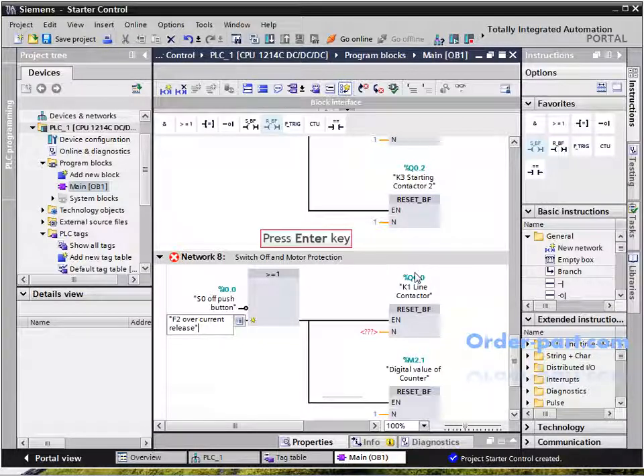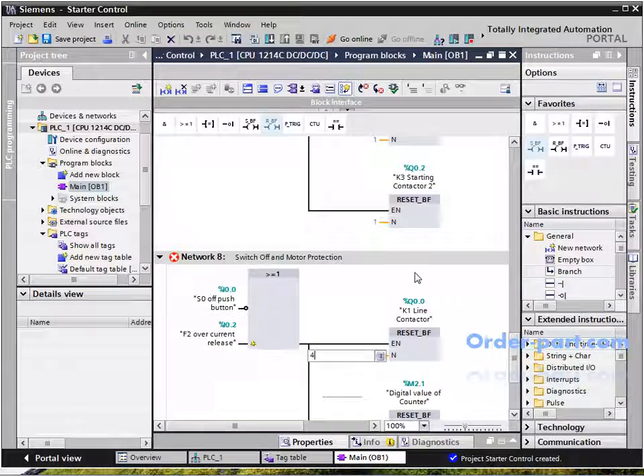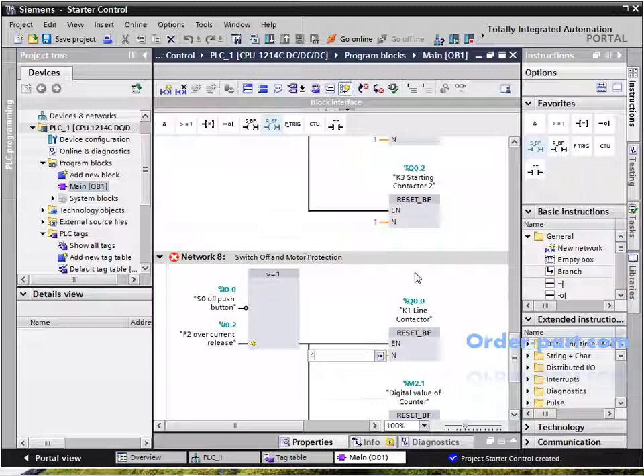In Network 8, if I0.0 is off or the F2 over-current release button I0.2 is on, it resets all contactors from K1 to K4 and sets the digital value of the counter to zero.